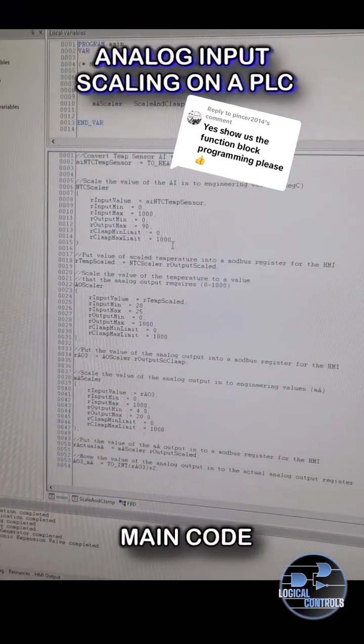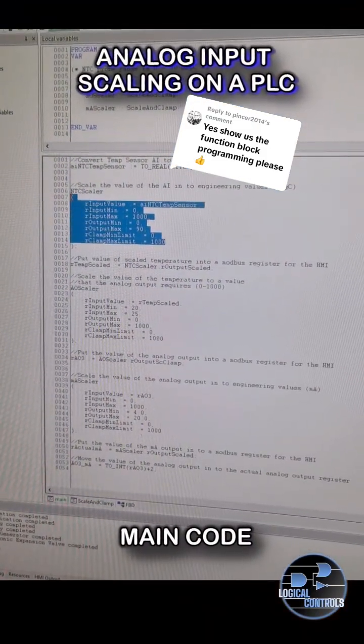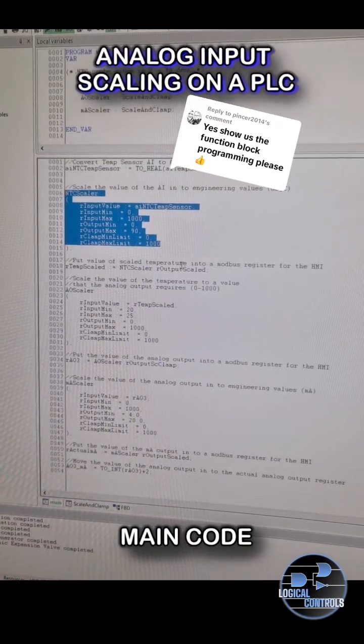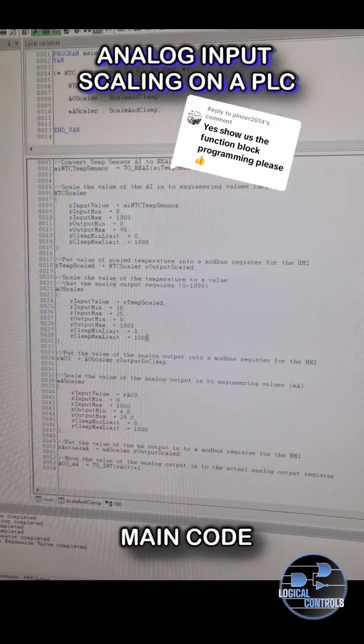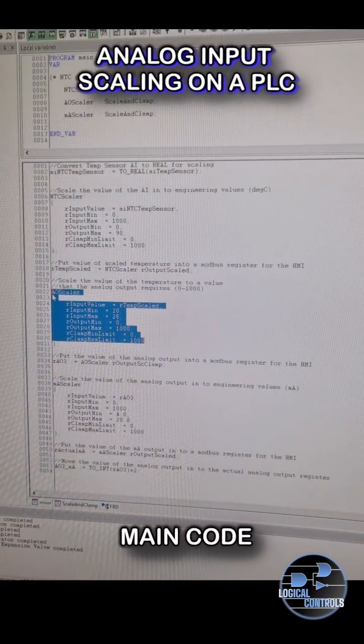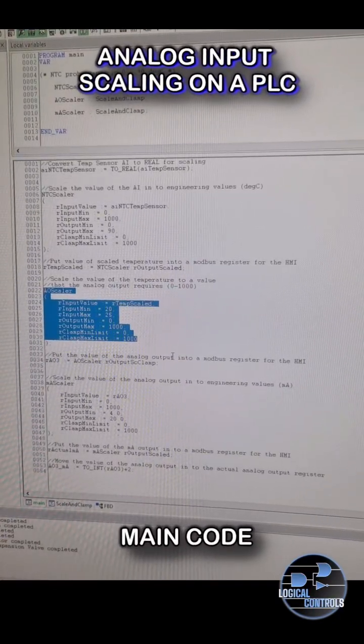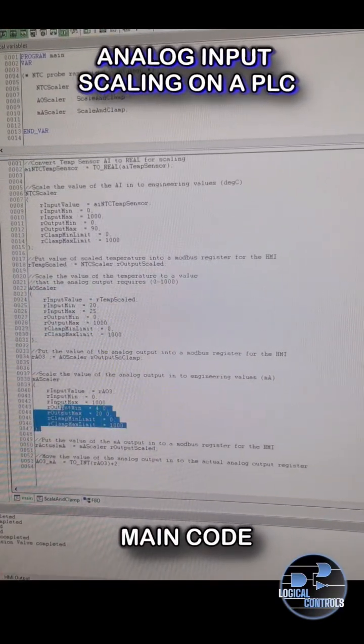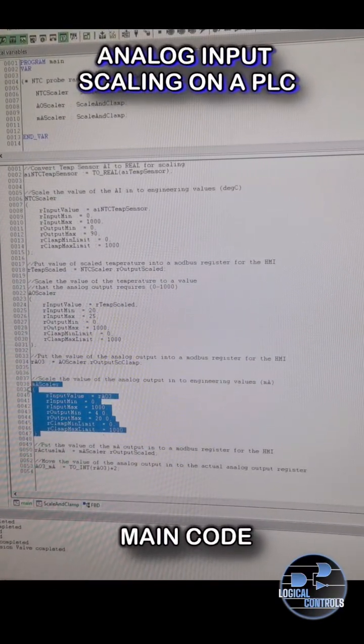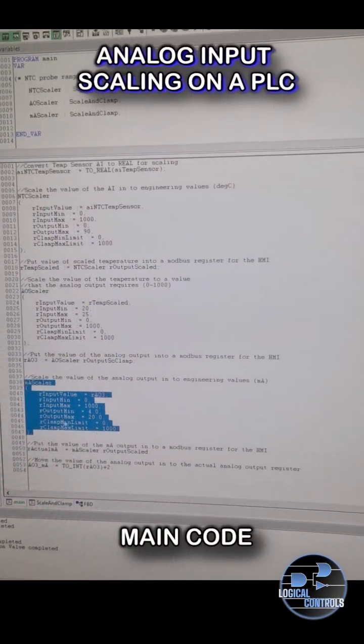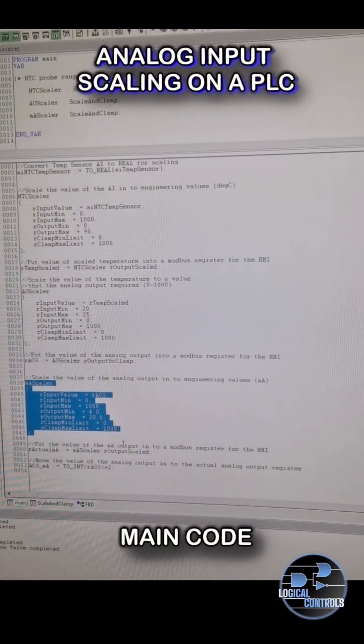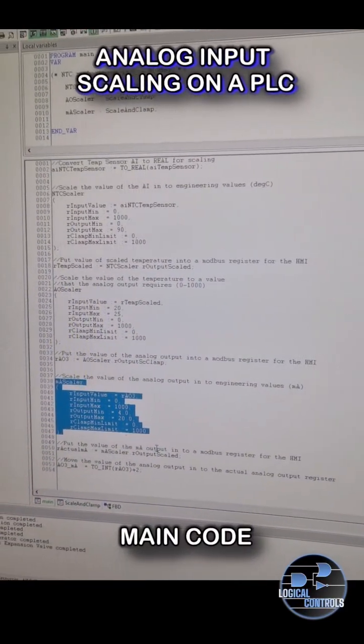Let's take a look at it now. So this is the main program, and it all looks a bit scarier than it actually is because a lot of it's just comments, but really all we're doing is using three function blocks. The first use of the function block is to take the raw analog input and convert it into a temperature. The second use is just to take that temperature and convert it into a value that the PLC needs for the analog output. And the last use is just to convert it back to a 4 to 20 milliamp so I can show it on the HMI.